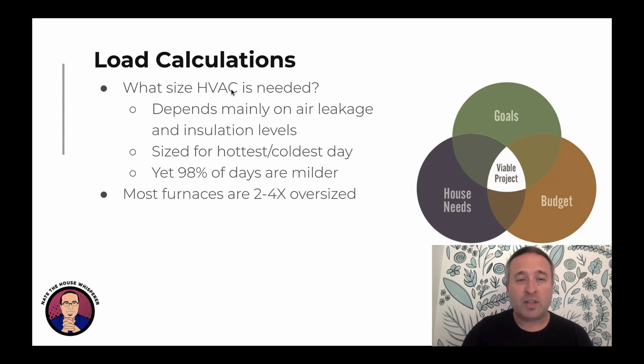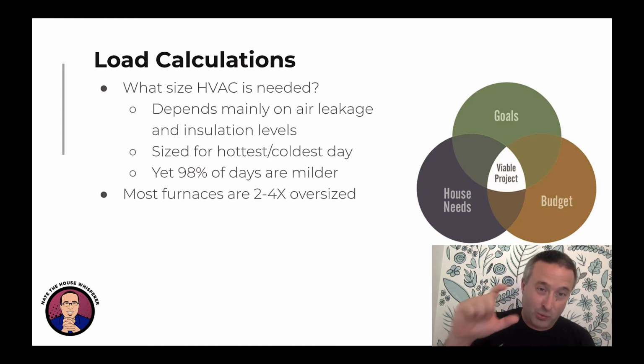So what size HVAC is needed? This depends mainly on air leakage and insulation levels. The exception would be if you're down south, windows do matter more. Windows affect cooling. They don't really change heating that much. And then obviously it's sized for the hottest and the coldest day of the year. The key thing though is if you're talking 1% design temps, you're talking the hottest 88 hours of the year and the lowest 88 hours of the year. 98% of the year is in between those. So you really want to size for that if you want comfort.